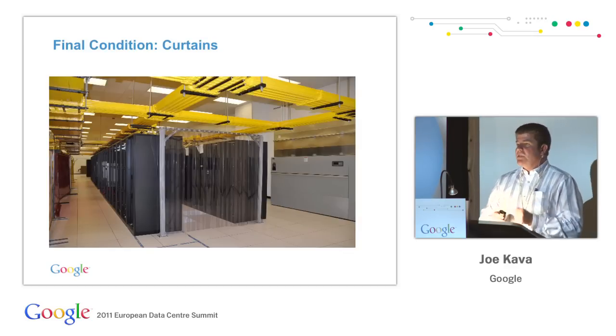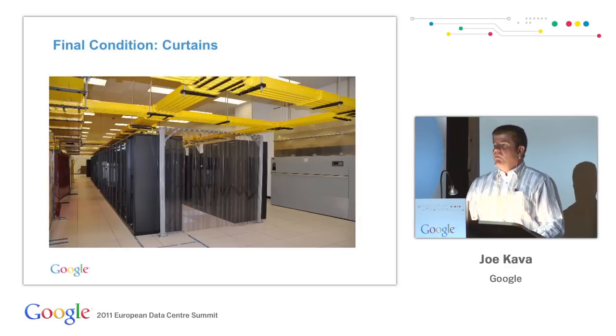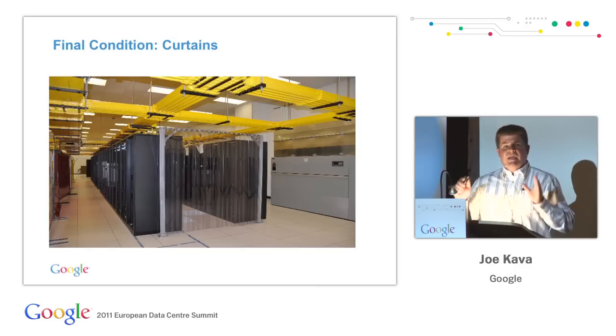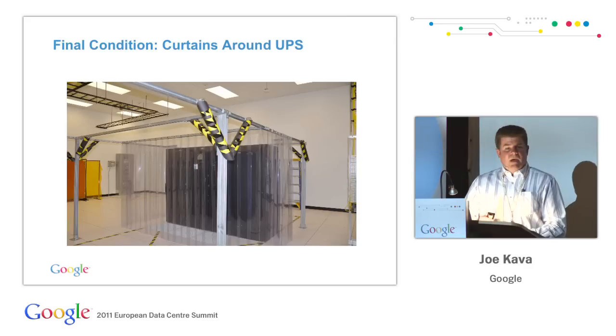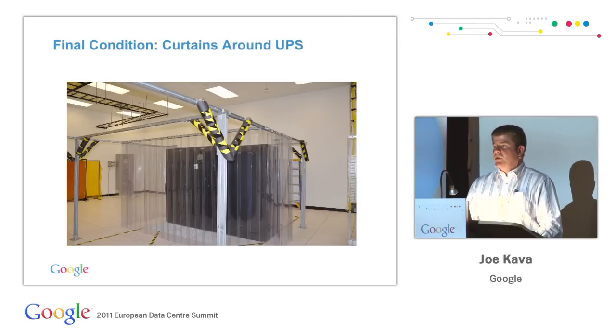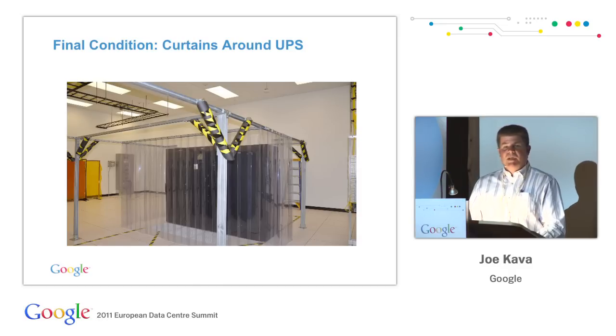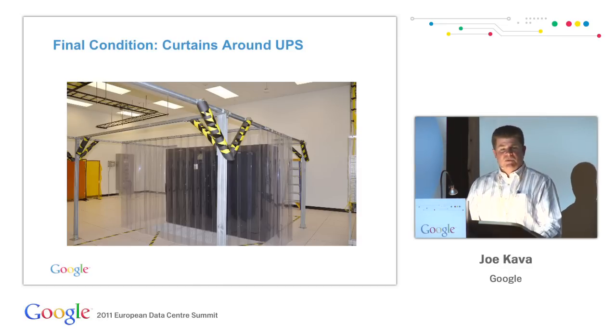The meat locker curtains at the end of the cold aisles. This was, once again, very inexpensive, easy to install, and didn't require any equipment shutdown to implement. Also, we fully contained the UPS units with these meat locker curtains so that we can maintain a slightly lower temperature in front of the UPS battery cabinets and get really good cold aisle isolation right around there.